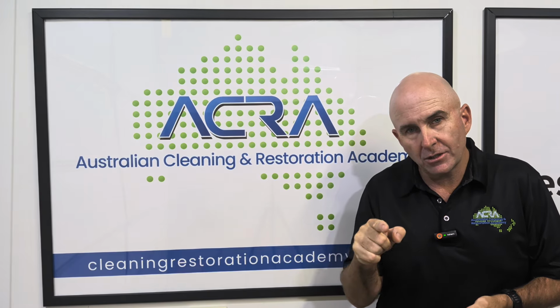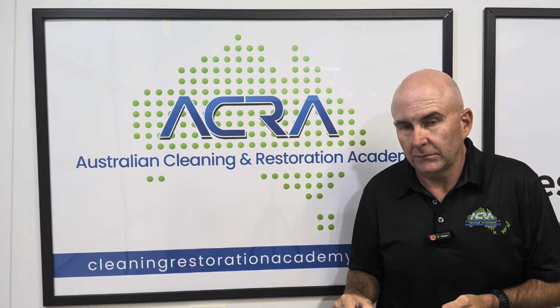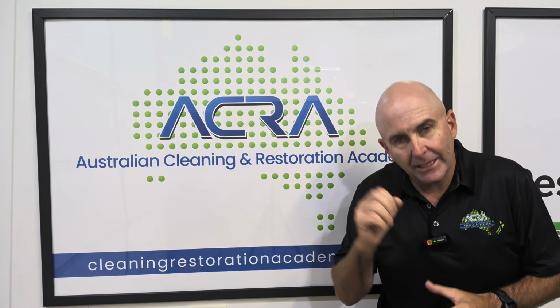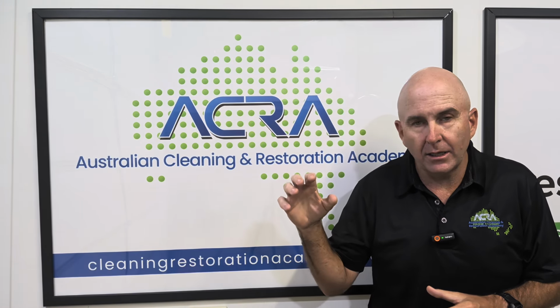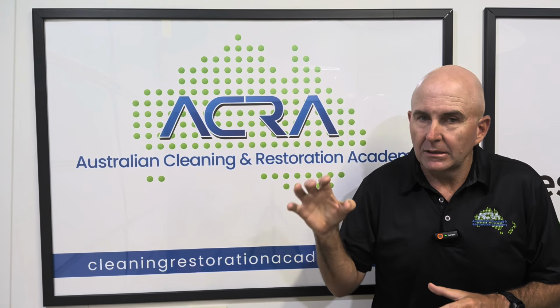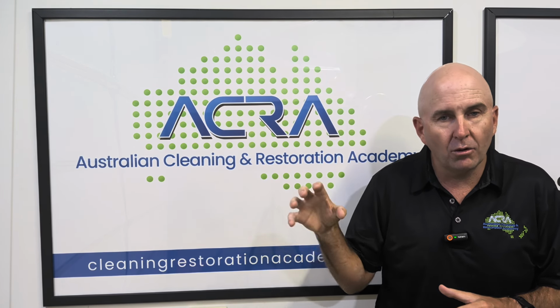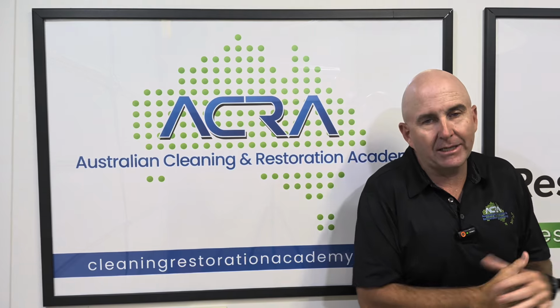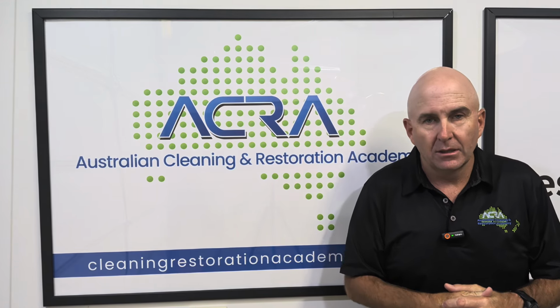So what are you writing? If you're going to write 2% on concrete, you can't do that. You have to have some letters behind it. If I'm going to be writing on the particle board 15%, I have to have some letters behind it, or that meter has to be calibrated to that material.